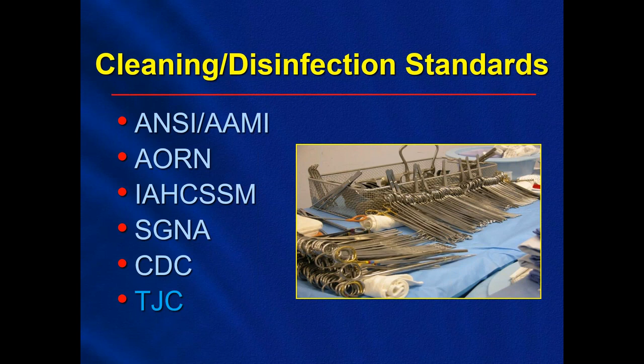So through all of the recommendations from all of the organizations and manufacturers' IFUs, it became evident that certain steps must be followed and that they are similar in nature. And there are 10 critical steps in the cleaning and reprocessing of flexibles that have been identified. They are point of use or bedside cleaning, leak testing, manual cleaning. You'll see manual cleaning has a little asterisk there. That's because the manual cleaning process alone has numerous subcritical factors involved. Factors such as dilution rates of your enzyme, water temperature, the use of the enzymatics, rinsing, etc. Then you have visual inspection, verification or validation, sterilization and high-level disinfection of your scopes, drying, transport, storage, and documentation.